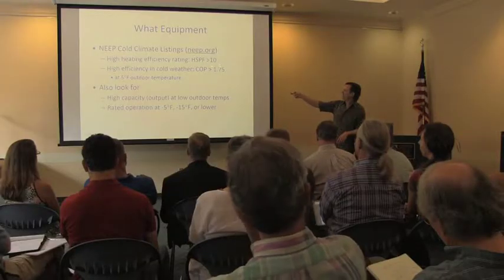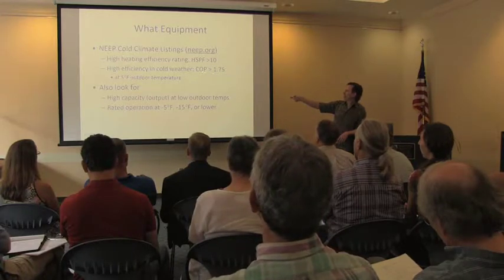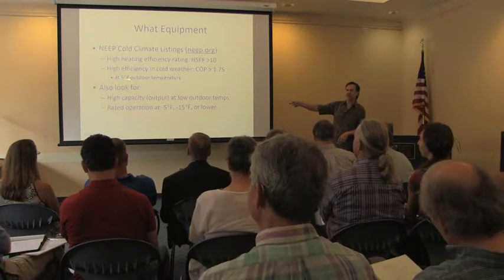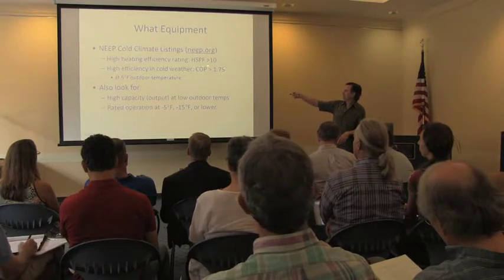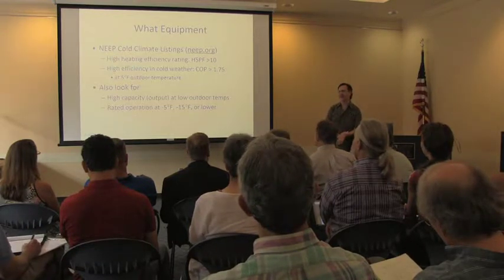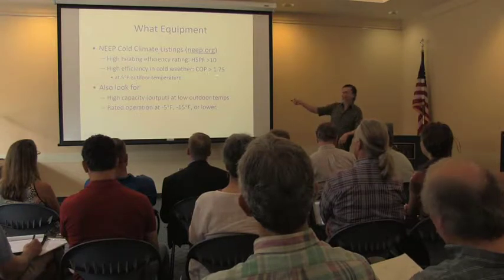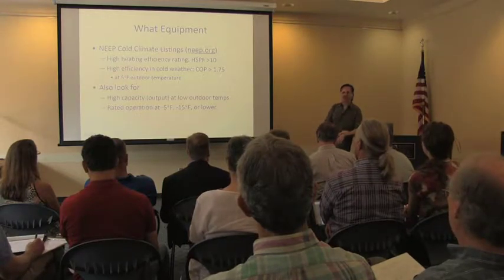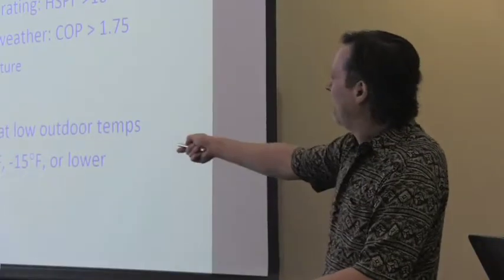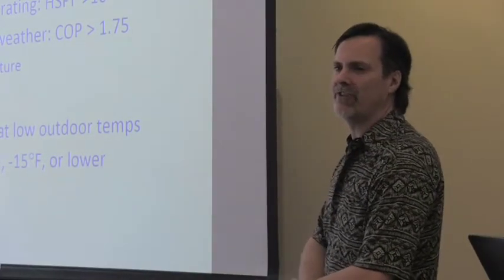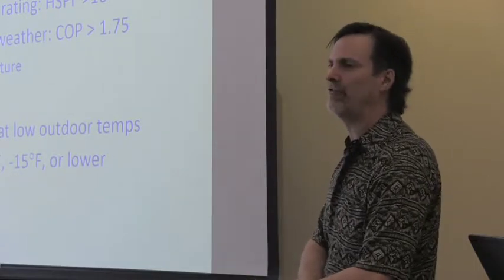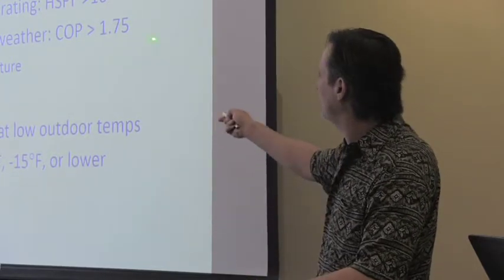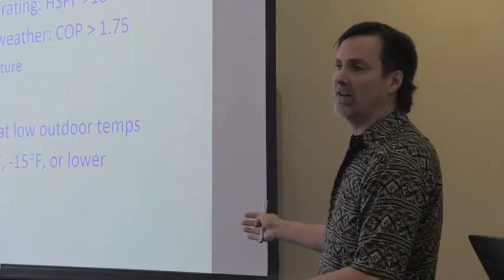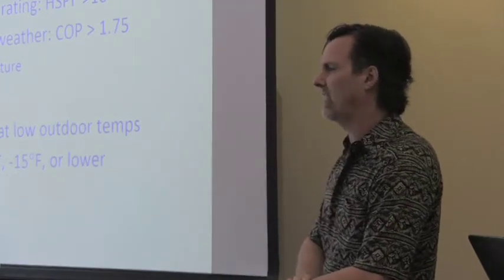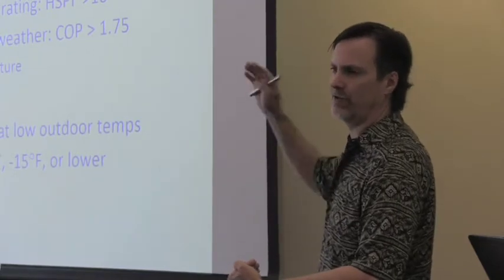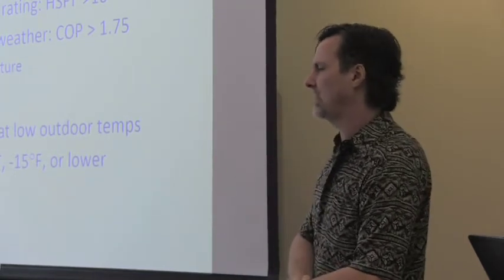So that's one requirement. For the cold weather performance, at 5 degrees outdoor temperature, the equipment has got to have a coefficient of performance of at least 1 3/4. Okay? So it's true that's not as good as 3 or 4 or 5, but that's at 5 degrees outdoor temperature. There aren't that many hours of the year, even in a cold climate, where the temperature is 5 degrees or colder. Generally, these things have COPs that are well over 2, even at temperatures of 10, 15 degrees Fahrenheit. And most of your heating hours in the year are going to be at higher temperatures where the efficiencies are even higher.